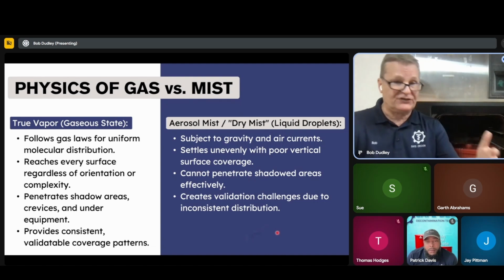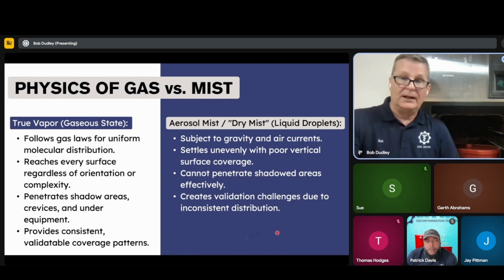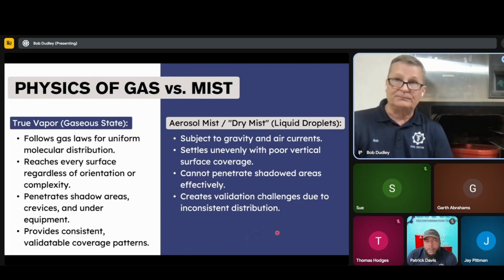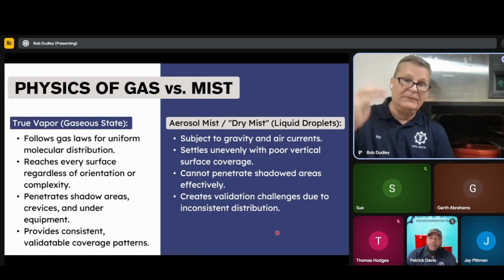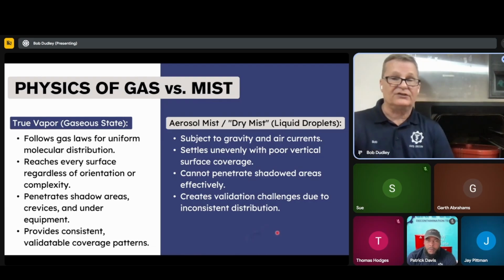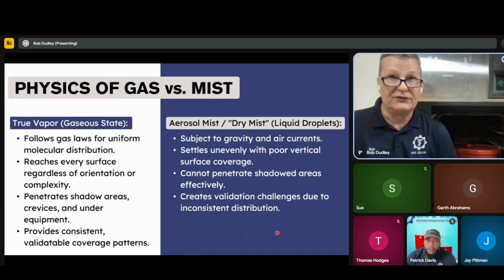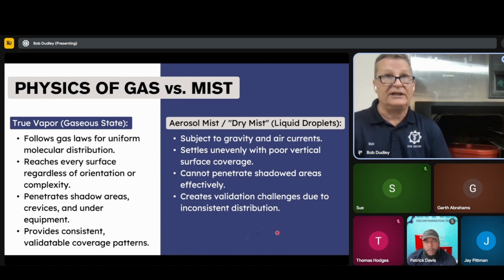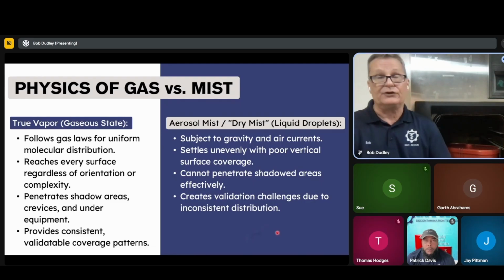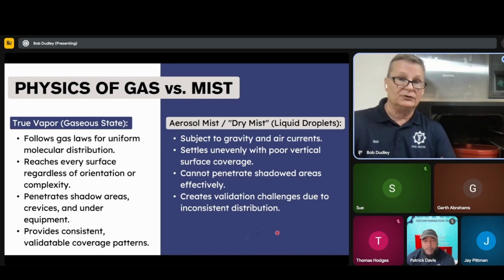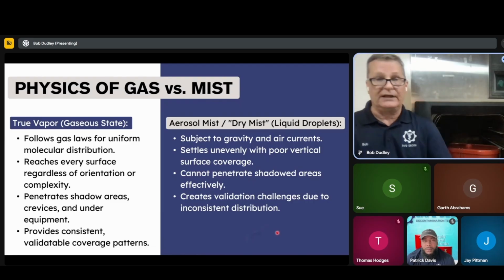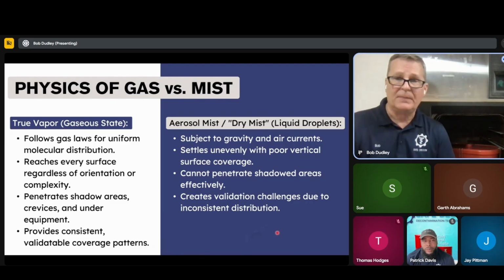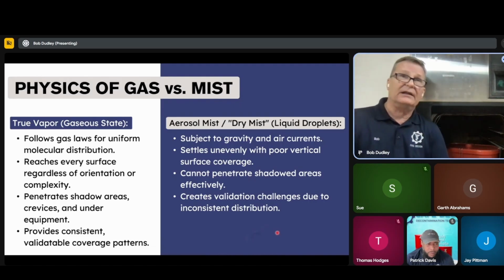So as long as it's in gaseous state, it tends to permeate things really, really good. When it turns into a mist, you can look at it very similarly to the dew in the air in the morning. If you look, it's all over your car, it's on the top, but if you look underneath things, there's no mist underneath. That mist or the water droplets will get on things, but the coverage is actually not as good. And when you get to the mist part, especially in autoclaving and decontamination sterilization, when you start getting that mist or you start seeing that steam in the autoclave, you're going to start getting the insulation and blocking factor of the steam. And we'll get into this when I start getting into steam saturation. But I just want you to know that gas is steam gas.